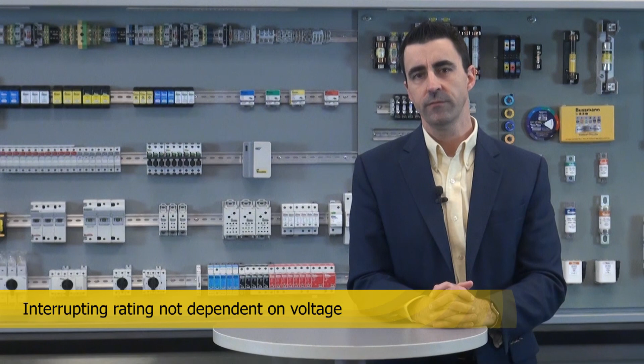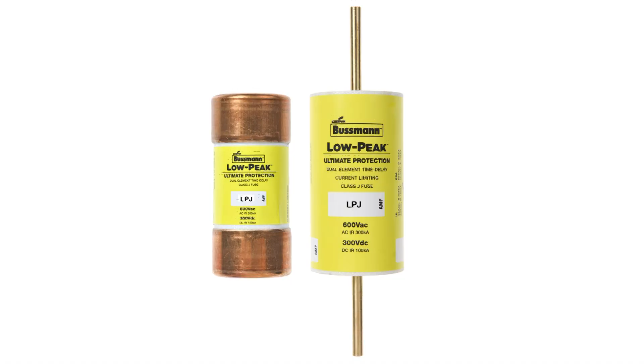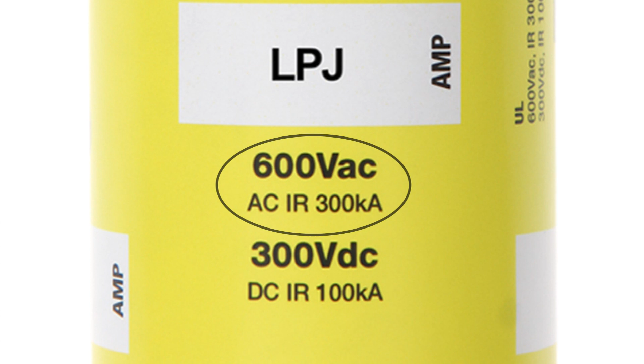The National Electrical Code in Section 110.9 requires equipment intended to break current at fault levels to have an interrupting rating sufficient for the available fault current. The fuse interrupting rating is not dependent on a particular voltage when applied within its rating. For example, a 600 volt rated LPJ fuse has a UL listed 300 kA interrupting rating for any voltage up to 600 volt AC. Whether for the initial installation or system updates, a fusible system can maintain a sufficient interrupting rating throughout its life. There is little need for additional fault current calculation or worry that the fuse will be misapplied due to an improper interrupting rating.